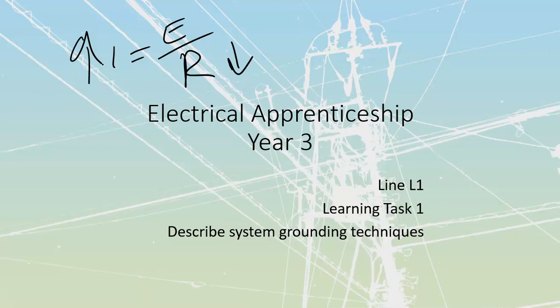If we do have these type of systems, we're going to need to have associated alarm devices that are going to monitor and send either a trip signal to the overcurrent or send some sort of a warning so that we understand what is going on. They are a safer system though, and we're going to see them predominantly in the high voltage sections because they do limit the amount of current, which means that we're going to have much less AFIE, or arc flash incident energy.